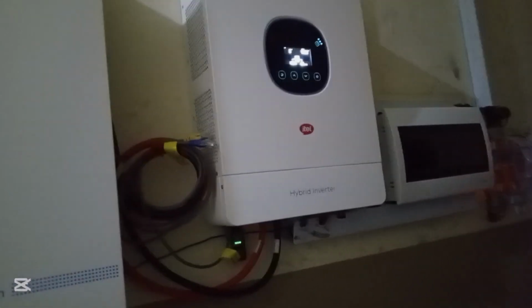Please, I want to re-emphasize on this. Earthing is very important for high voltage system, but the inverter should be earthed differently from the solar panels.